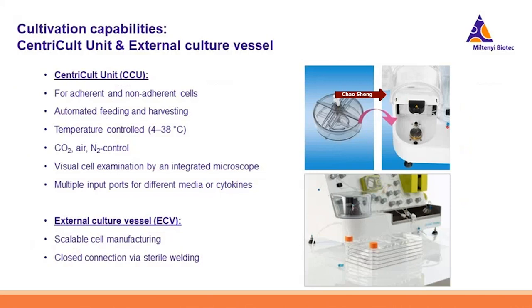This part supports adherent and non-adherent cell cultures. It works basically like a small incubator where you can control the temperature from 4 to 38 degrees inside the CCU. You can also control the concentrations of air and CO2, and visualize your cell cultures because we have integrated a small camera under the chamber. There are also multiple input ports available to support your cell cultures with different mediums and cytokines. The CentriCult Unit offers 100 square centimeter surface space. If larger surface space and cell numbers are required, you could connect big external culture vessels, such as multi-layer cell stacks, using sterile welding technology.